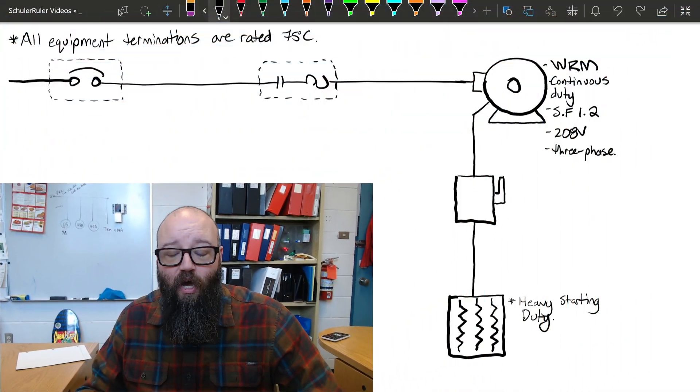We're going to start off with the stuff that really doesn't change from any other motor branch circuit calculation — the branch circuit conductor calculations, the motor supply conductor calculations, and the overload calculations. Then we'll take off into the stuff that's more specific to wound rotor branch circuits, starting with the overcurrent calculations and then the secondary conductors from the motor to the controller and from the controller to the resistor bank.